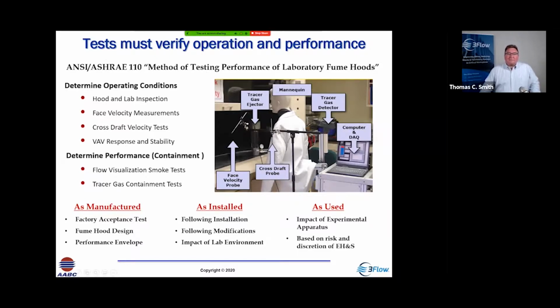Now, you can get into this business fairly simply and with some investment, be able to do it. The problem I have right now is that it's going to change. And when it changes, we're not quite sure. It could be 6 months, could be a year and a half, probably a year and a half to 2 years away. So is that enough time to recoup the investment in the equipment to do ASHRAE 110 with SF6? There's also the impact on the environment. The more we generate SF6, it's a very strong global warming gas. And so we're putting a lot of it out in the environment. And do we want to do that during the interim?